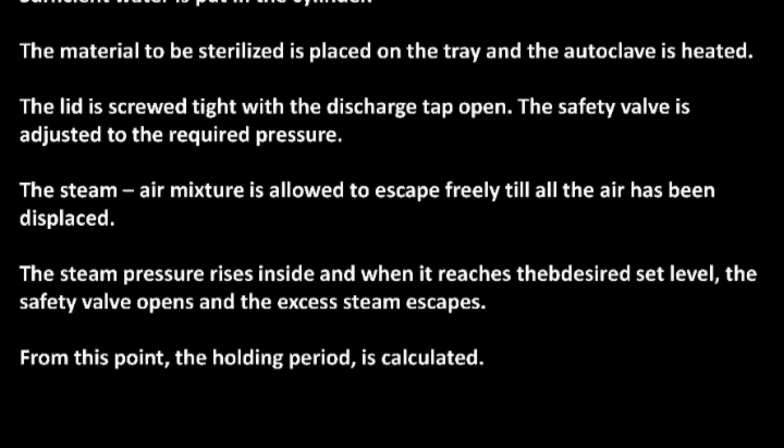Sufficient water is put in the cylinder, the material to be sterilized is placed on the tray, and the autoclave is heated. The lid is screwed tight with the discharge tap open, and the safety valve is adjusted to the required pressure. The steam-air mixture is allowed to escape freely until all air has been displaced. The steam pressure then rises inside, and when it reaches the desired set level the safety valve opens and excess steam escapes. From this point, the holding period is calculated.